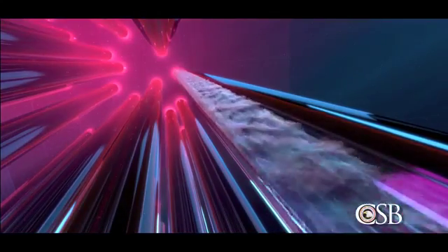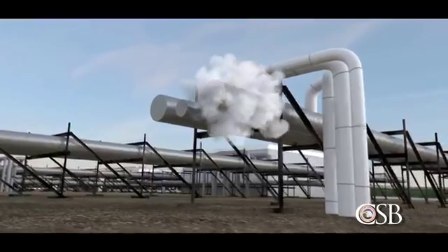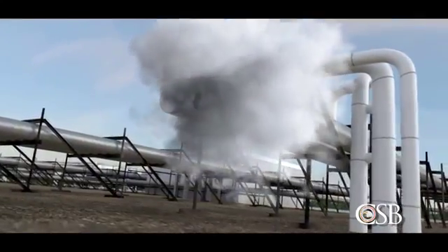The control system reset triggered a valve to open, and low-temperature liquid ammonia was fed back into the evaporator coils before removing the hot ammonia gas. This caused the hot, high-pressure ammonia gas to rapidly condense into a liquid. A vacuum was created where the gas had condensed. The void sent a wave of liquid ammonia through the piping, causing a sudden pressure surge known as hydraulic shock. The pressure surge ruptured the evaporator piping manifold inside one of the freezers and its associated 12-inch piping on the roof of the facility.